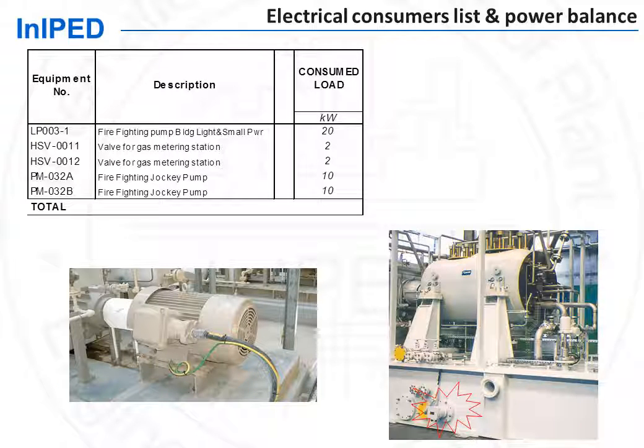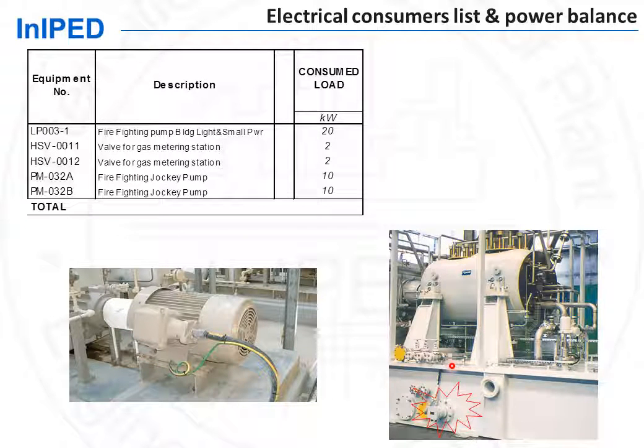The starting point of the electrical engineer is to draw the electrical consumers list. It consists of making an exhaustive inventory of all plant electric power consumers. These include obvious process consumers, such as pumps, as well as some hidden consumers, such as this lube oil heater inside a compressor package.